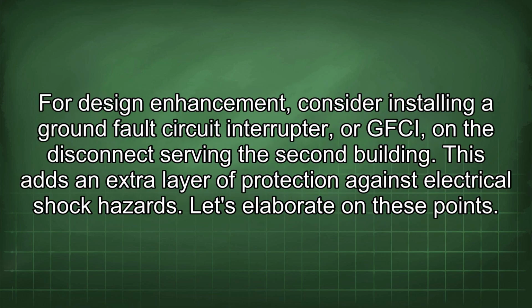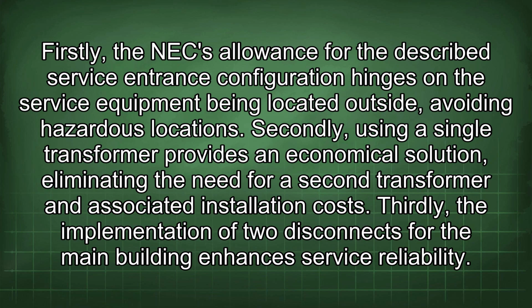For design enhancement, consider installing a ground fault circuit interrupter, or GFCI, on the disconnect serving the second building. This adds an extra layer of protection against electrical shock hazards. Let's elaborate on these points. Firstly, the NEC allowance for the described service entrance configuration hinges on the service equipment being located outside, avoiding hazardous locations.